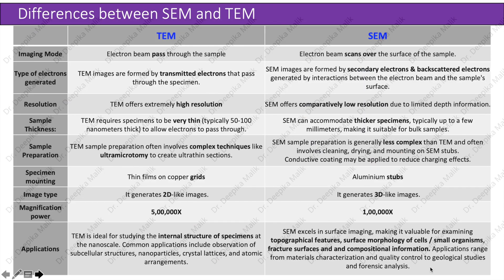The next slide shows the major differences between SEM and TEM. Imaging mode: in TEM, the electron beam passes through the sample; in SEM, the electron beam scans over the surface. Type of electrons: TEM images are formed by transmitted electrons, whereas SEM images are formed by secondary and backscattered electrons. Resolution: TEM offers extremely high resolution, whereas SEM offers comparatively lower resolution due to limited depth information. Sample thickness: TEM requires specimens to be very thin — typically 50 to 100 nm — while SEM can accommodate thicker specimens, typically up to a few millimeters, making it suitable for bulk samples.